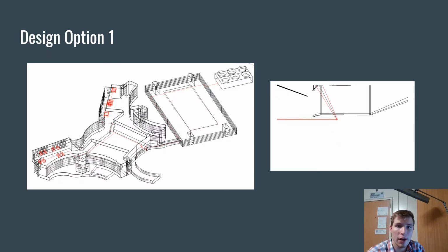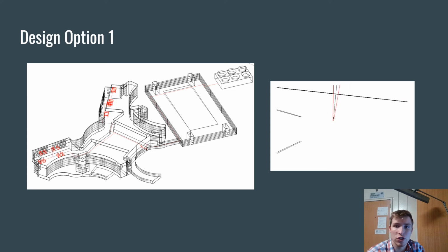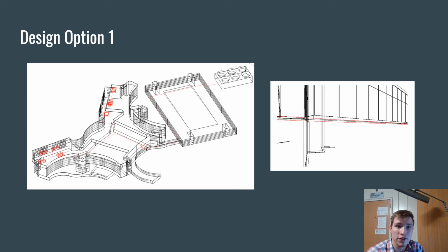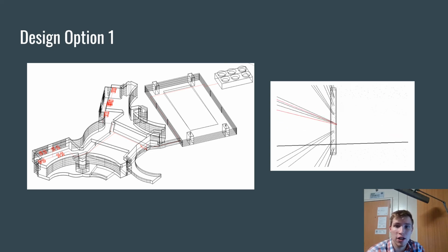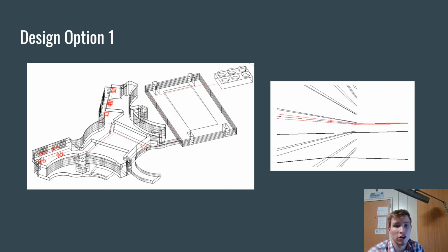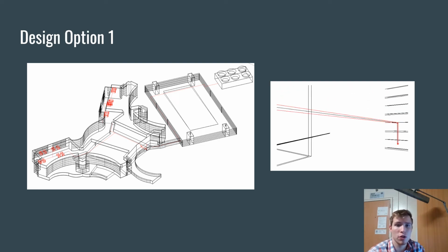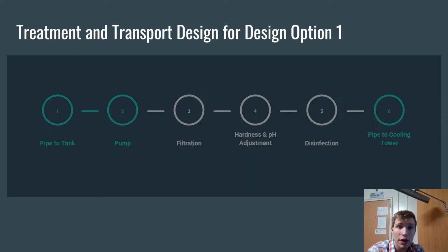On this slide, we have a CAD model and a short animation that demonstrates how the design is laid out in the facility. The condensate starts at the air handling units. It is drained into the mechanical room where it is treated and then pumped through the parking garage to the cooling tower. In the mechanical room, there is a series of equipment used in this project. It starts with the condensate entering a tank. Once the tank is full, a float switch will start a pump, which transports the condensate through a filtration and a disinfection system. After this, the condensate travels to the cooling tower.